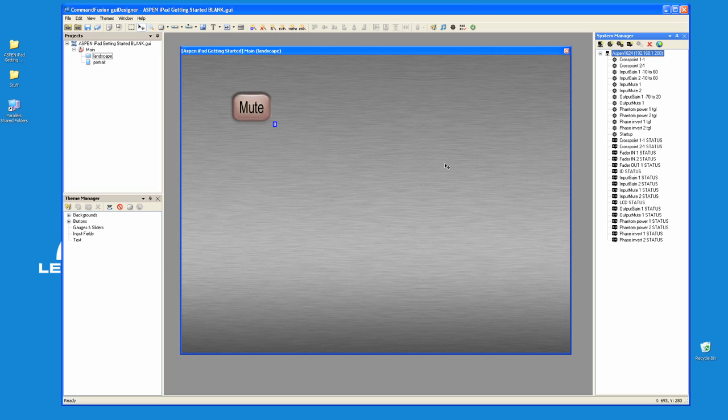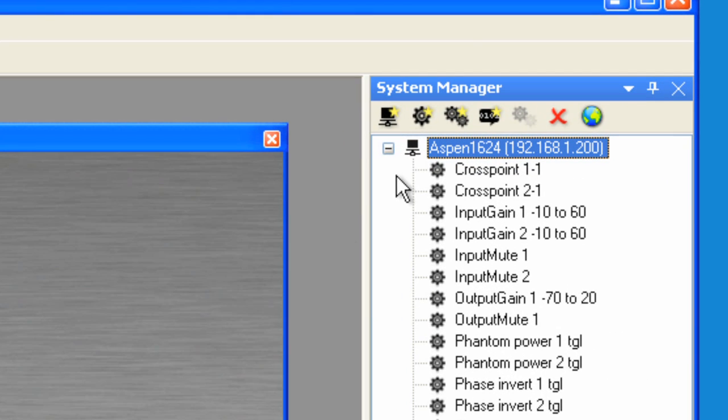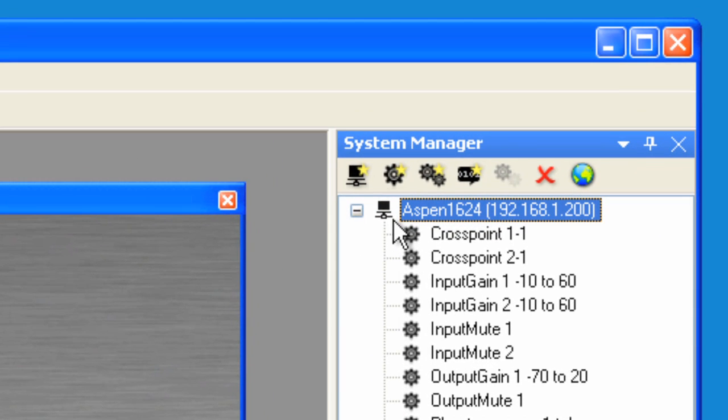Before we can send a command to the Aspen box, we must make sure that we set up the same IP address in the Aspen device that we set up in System Manager, which in this case is 192.168.1.200. So let's do that now.